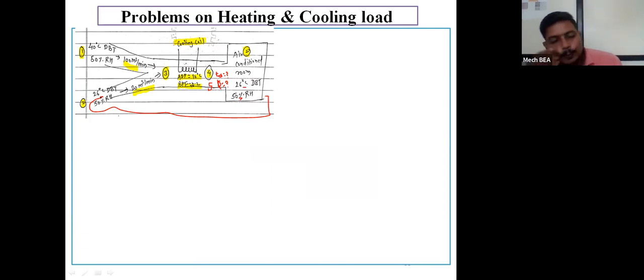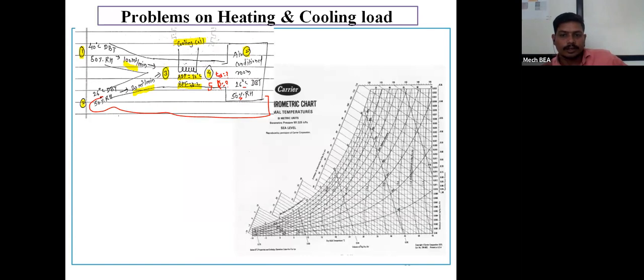Okay. Now here I have to calculate the RSHF line or the value of RSHF, and again I have to calculate the cooling load capacity of the coil. So for that purpose, first of all, I am going to locate point number 1 on the psychrometric chart.